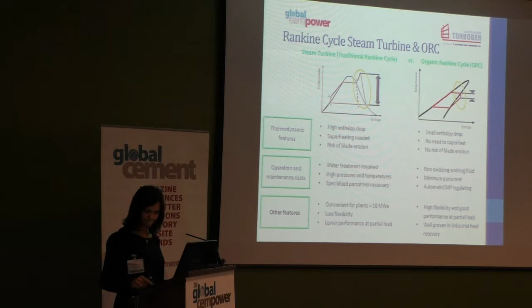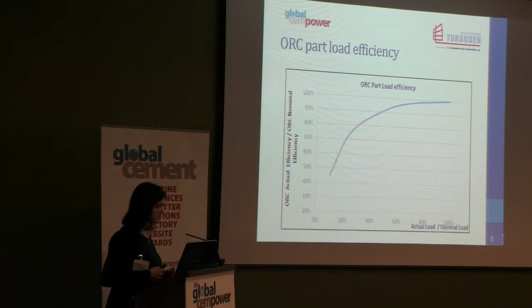This is an example of the partial load efficiency of the ORC. As said, we can work down to 10% of the load. On this axis we have the load, and here is the efficiency. At 100% load we have maximum efficiency, while at 50% load the efficiency decreases a little but is still quite good. It's even possible to work down to 10% of the load.